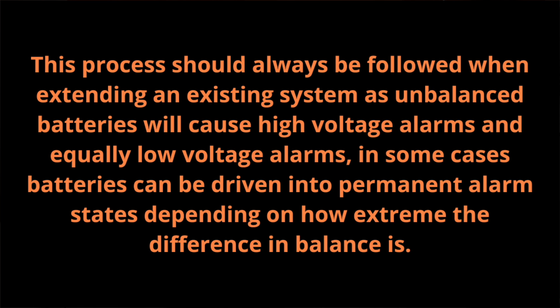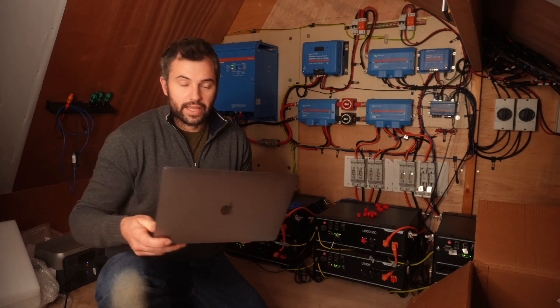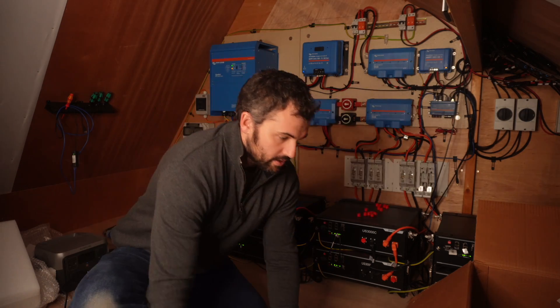I've got no quibbles about what he says at all, but this needs yet another version. This process should always be followed when extending an existing system, as unbalanced batteries will cause high voltage alarms and equally low voltage alarms. In some cases, batteries can be driven into permanent alarm states depending on how extreme the difference in balance is. Yeah, that makes sense.